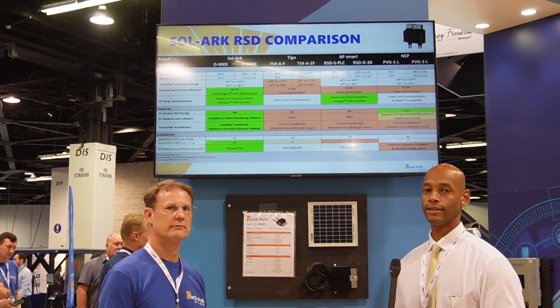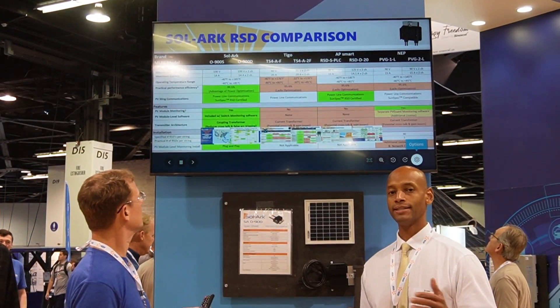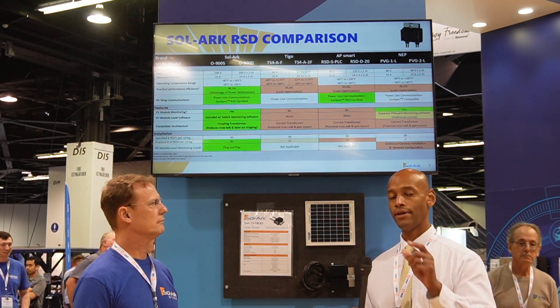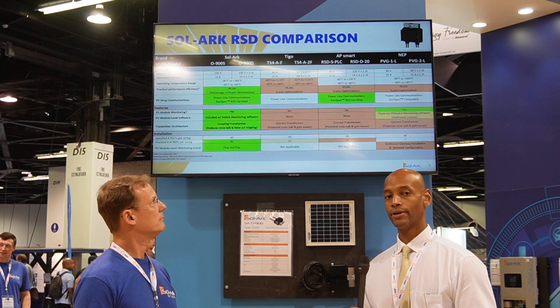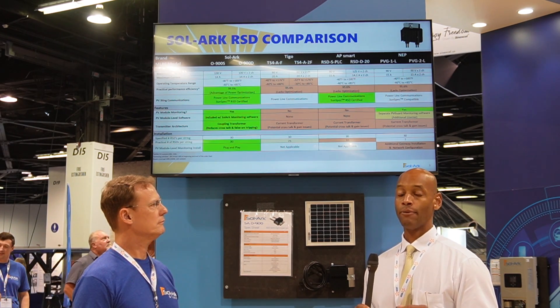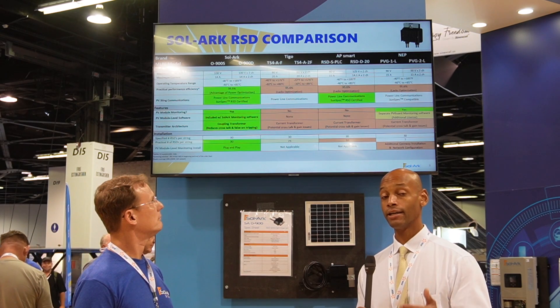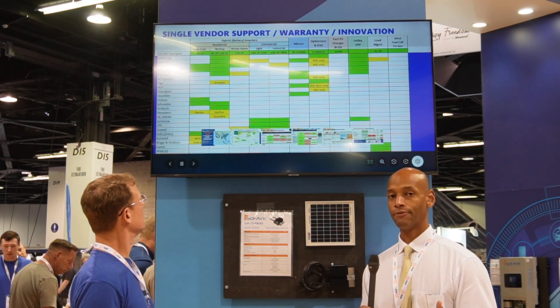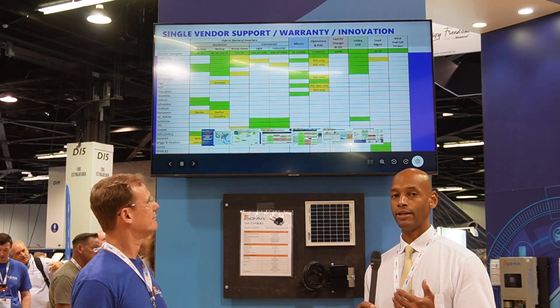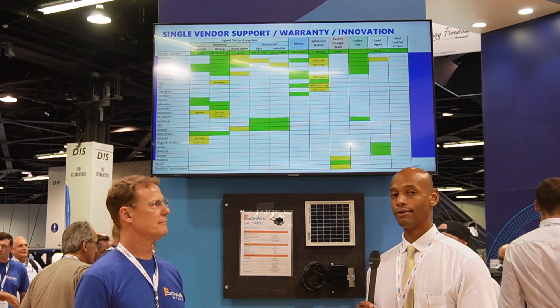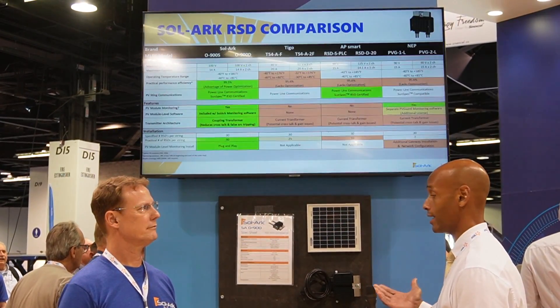That makes sense. To give you some context: traditional solar, about eight years ago and before, was wired into high-voltage DC strings, and that high-voltage DC would be brought down to an inverter at ground level for DC-to-AC conversion. However, in cases where there was a fire in the building, firefighters cutting into the rooftop to vent the flames could hit that high-voltage wiring and cause injury or death. So the idea was to have a button at ground level that could rapidly shut down and remove all the high-voltage DC power. Optimizers are one solution that accomplishes that.